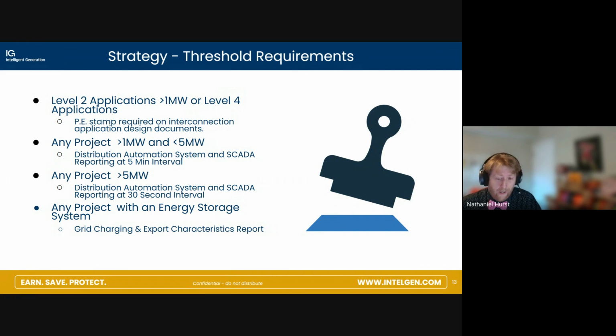Any project greater than 1 megawatt and less than 5 megawatts — and a reminder, this is all right out of the ComEd interconnection standards packet — you can go ahead and have a SCADA system with a 5-minute reporting interval. What this means is effectively your data acquisition system also has to report to ComEd on a 5-minute schedule. If you go over 5 megawatts, which once again gets into pretty rare territory, now you have to have your own SCADA reporting system that reports at a 30-second interval. What that means is that your telecom system to the site is going to level up pretty significantly.